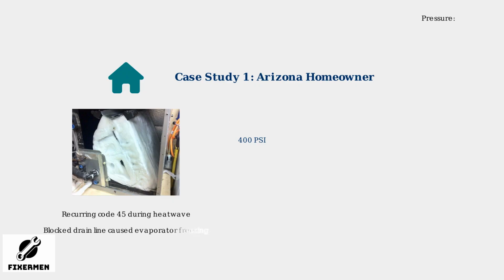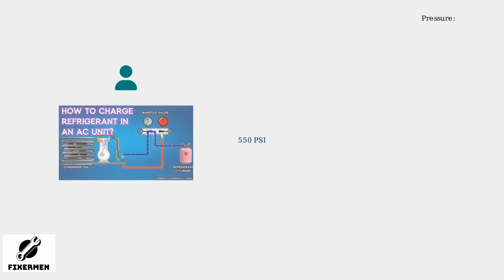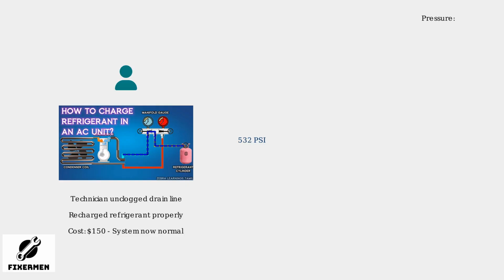Let's examine real-world case studies of error code 45 solutions. First, a homeowner in Arizona experienced recurring code 45 during a summer heat wave, with temperatures reaching 110 degrees Fahrenheit. The issue stemmed from a partially blocked drain line that caused the evaporator coil to freeze, restricting airflow and building excessive pressure in the system. A Carrier-certified technician diagnosed the problem, unclogged the blocked drain line, and recharged the refrigerant to the proper levels. The total repair cost was $150, and the system has been running normally since. This case demonstrates how airflow restrictions can lead to evaporator freezing and subsequent high-pressure lockouts.